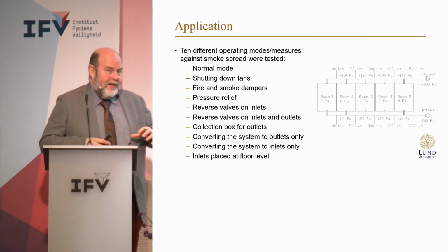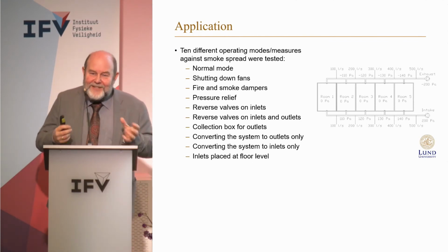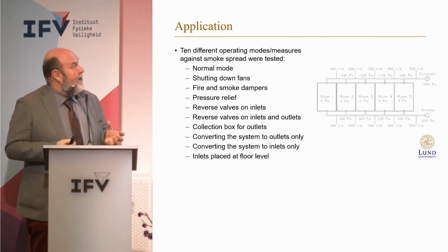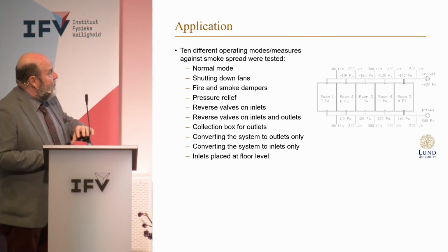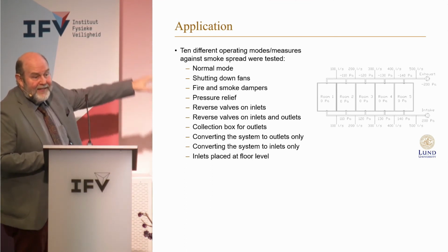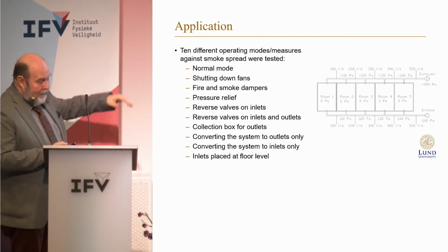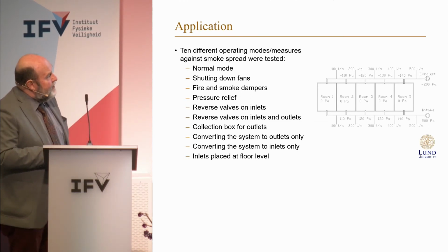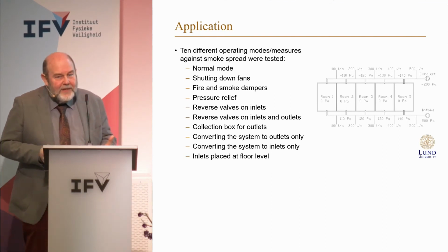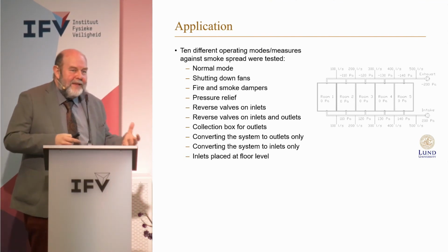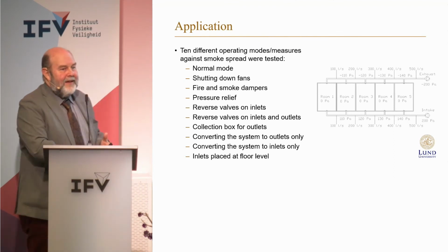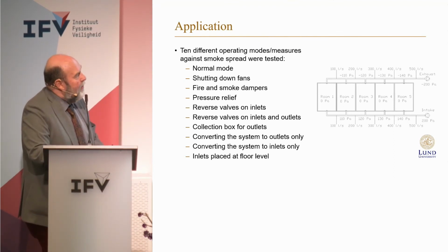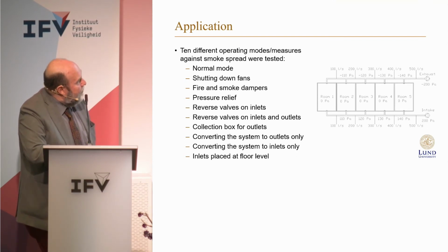And what we did is that we used the common knowledge in Sweden of what type of actions could be done in case you have multiple rooms and you would run, for instance, the normal mode. You could shut down those fans and look at what's happening. You get pressure reliefs and so on. I'm not going to list that because time is running out, but we used all these different types of strategies on this kind of 5-room setup with a fan system as it would be, at least in Sweden, not a strange situation. I have to explain a little bit that in Sweden we have rules where we allow certain leakage in case of fire between compartments or apartments, and then it's important to know whether that will happen.